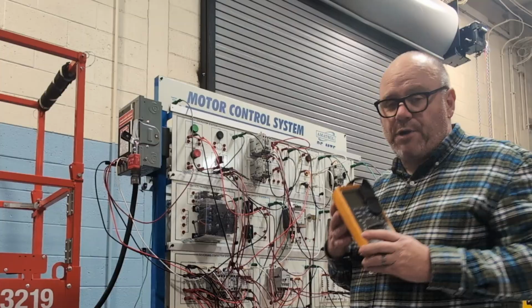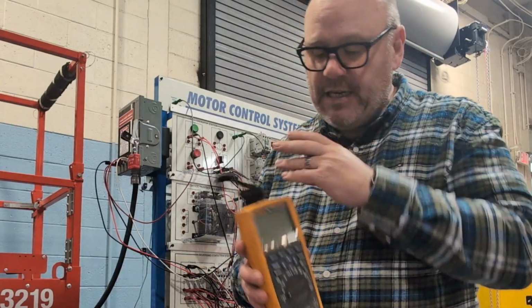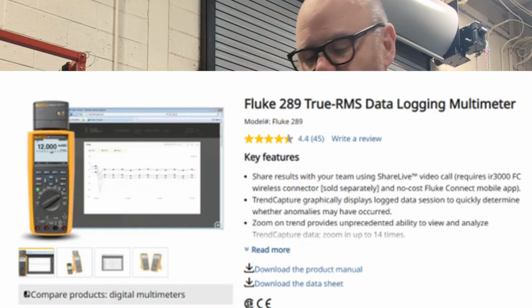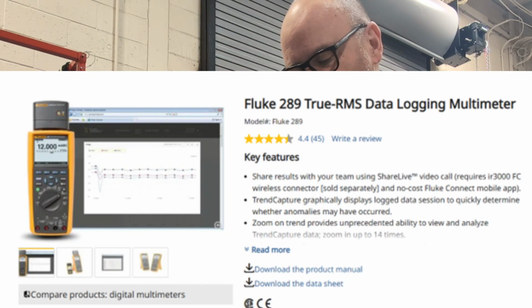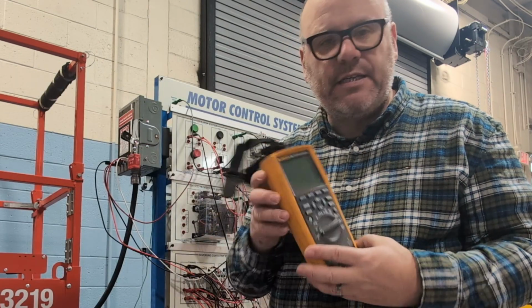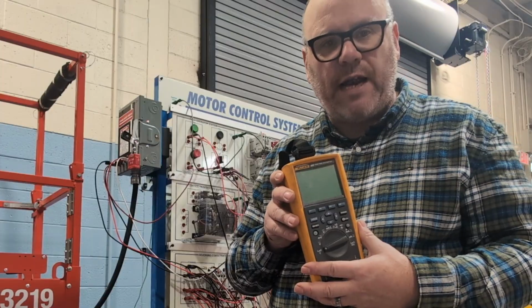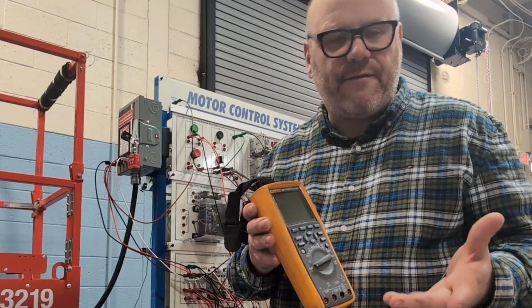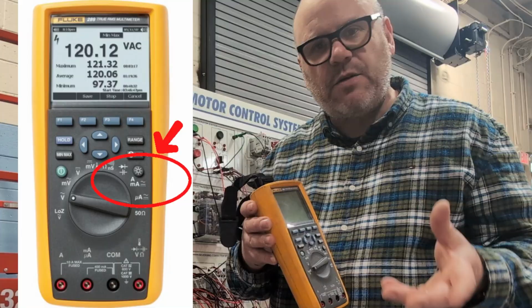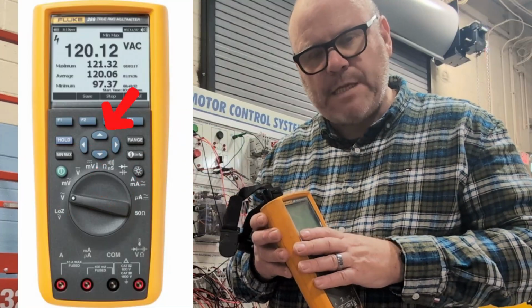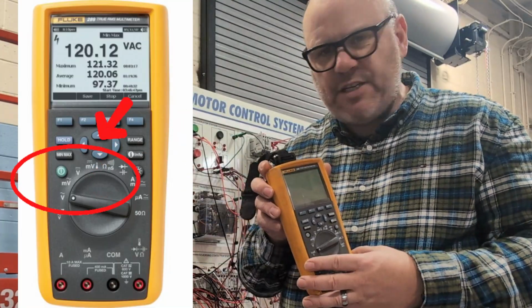Now we're talking about bread and butter. This is expensive, this is a process meter. Basically, what a process meter does, and your expensive meters, is give you the option to see lower amperage. In process work, you have something called 4 to 20 milliamps, 0 to 10 volts, and this can read it. Same deal, it's true RMS.